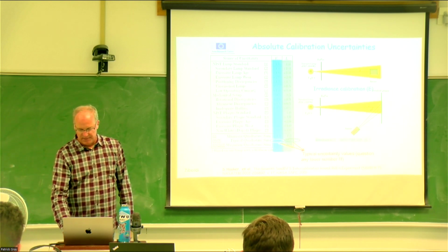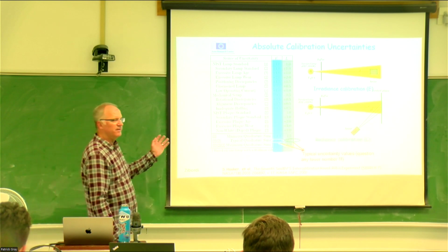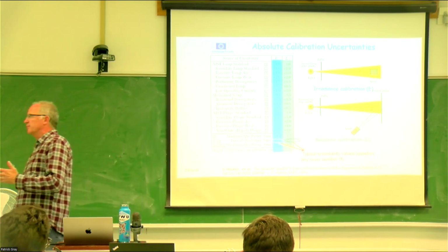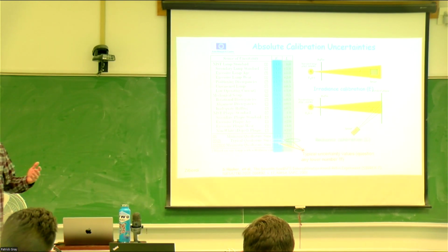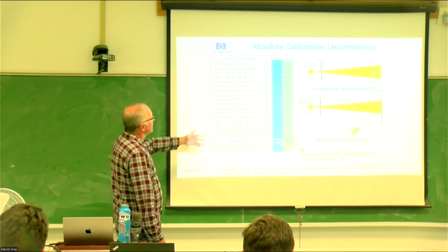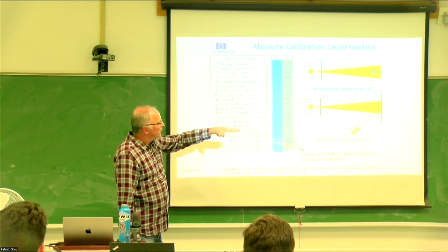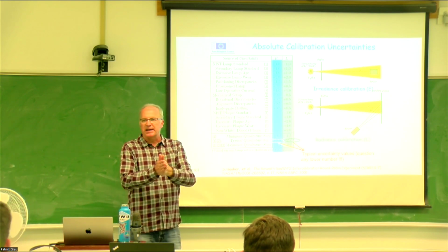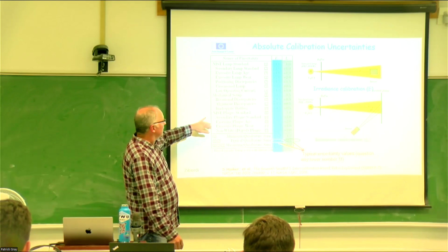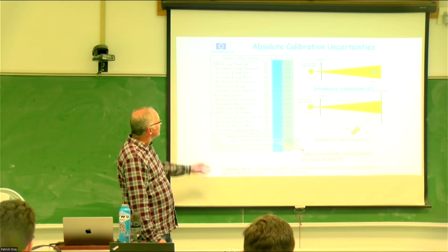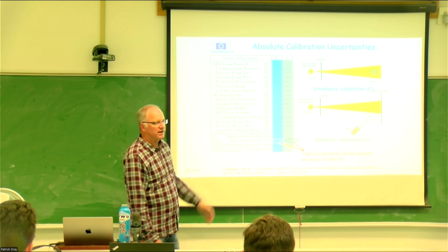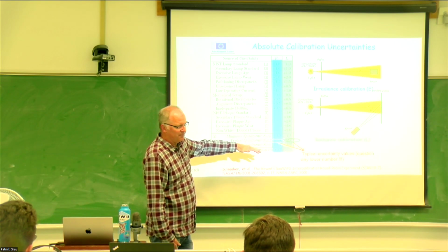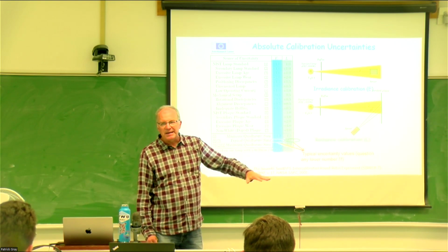All right. So we just talked about a handful of uncertainties in both processes. Here's a list of sources of uncertainty in doing both the radiance and irradiance measurement. There's inadequate mechanical setup to actually have it aligned right. Was it an unseasoned or a seasoned lamp? Is it getting too old? Did I put a thumbprint on it accidentally? You take all these things into account. And even NIST is about this low.